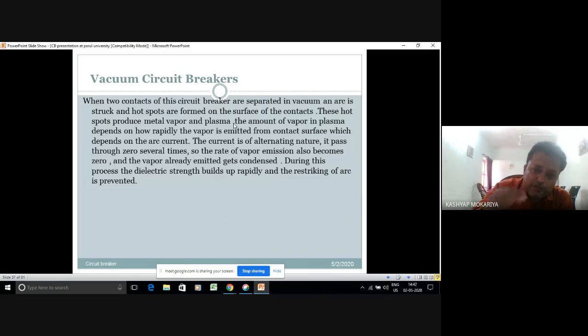Due to this superior property of producing metal vapor in proportion to the arc current rating, it has very fantastic arc quenching capabilities for a particular rating. In the industry where I was working, we were using this VCB for operating a 6.6 kV high tension motor. Again, I am repeating, the HT motors were rated for more than 160 kilowatt, with a supply of 6.6 kilovolt, and we were using 33 kV breakers for distributing the electricity on the whole industry campus by means of the VCBs.